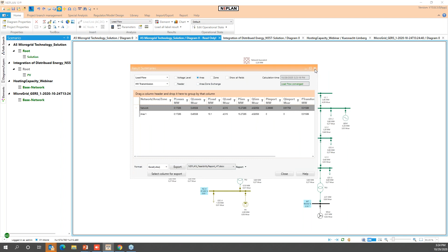Now, finally, if we disconnect the microgrid from the system by opening the two breakers, we have to enable one of the generators as the slack generator. Then we come to this case, where we work the system as an island. You will notice that the two breakers are open and that the generator became a slack source, because any system needs a slack bus bar or generator.